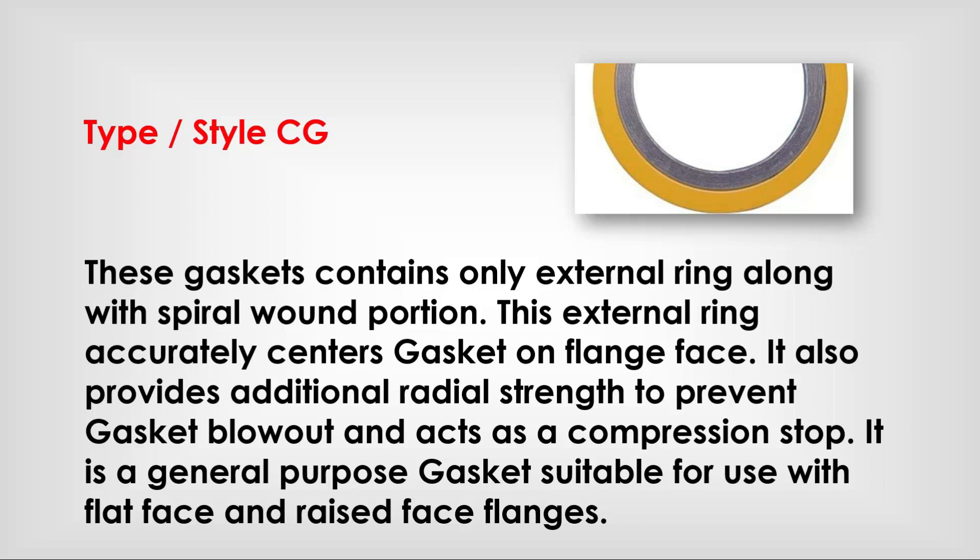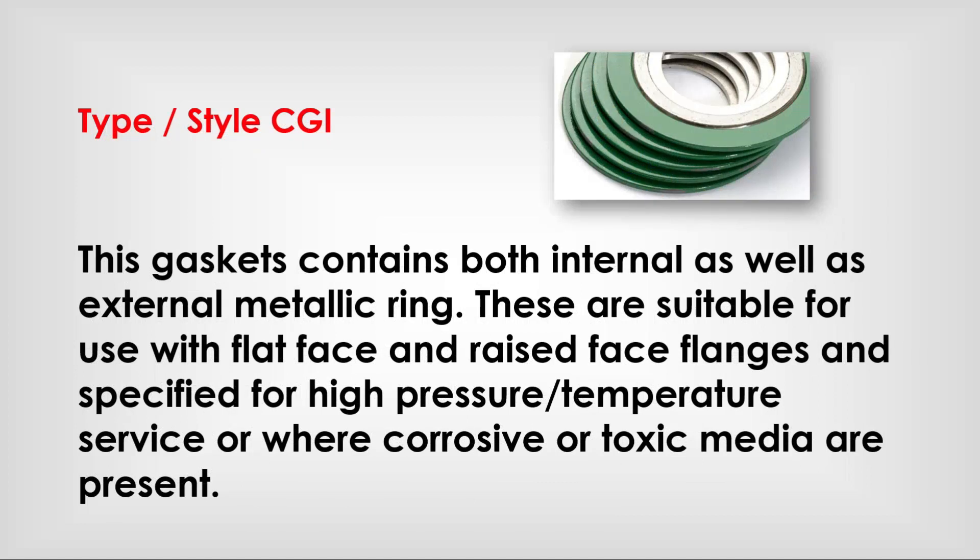Type style CGI: these gaskets contain both internal and external metallic rings. They are suitable for use with flat face and raised face flanges and are specified for high pressure/temperature services or where corrosive or toxic media are present.